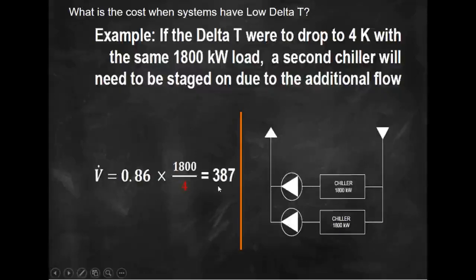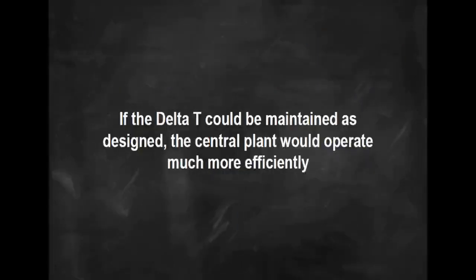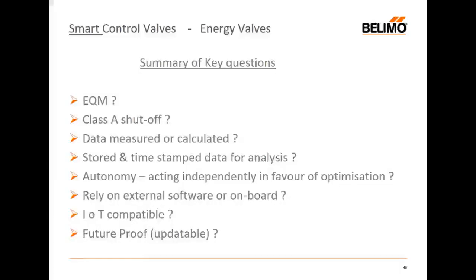And the problem was never the flow, the problem was never the chiller. The problem was at the coil, not managing the delta. By losing delta, we have a massive impact on the pump and on the production unit. If we managed the delta, then the plant would certainly operate much more efficiently. And this is where smart valves can help. They should have EQM, they should have Class A shut off.